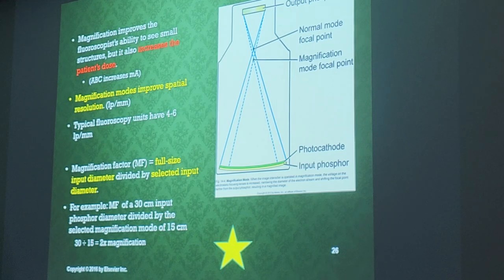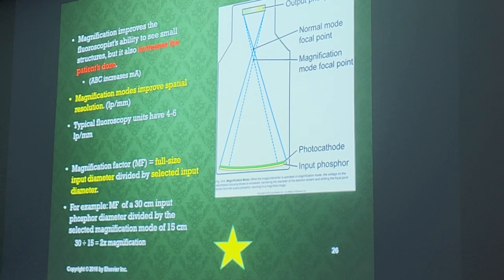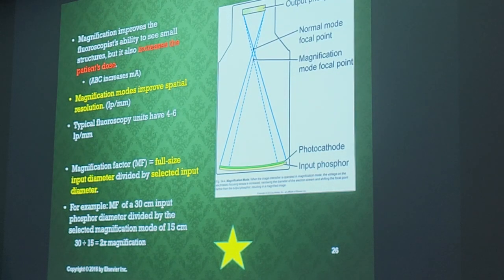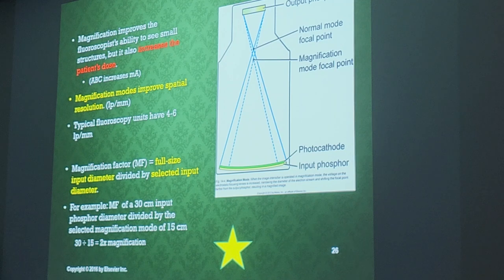If you have a question regarding magnification factor, it's straightforward. If you want the magnification factor of a 30 cm input phosphor and you're using 15 cm, you take 30 divided by 15 — the magnification factor is two. You take the full width divided by the centimeters you're using. For example, a 30 cm input phosphor using 23 cm: 30 divided by 23 gives your magnification factor.